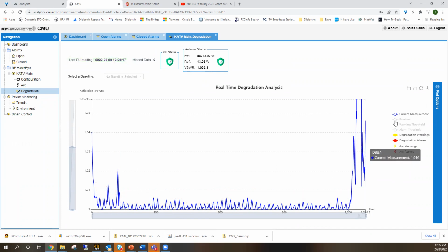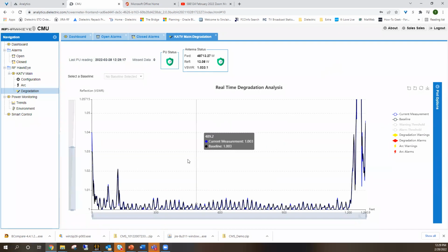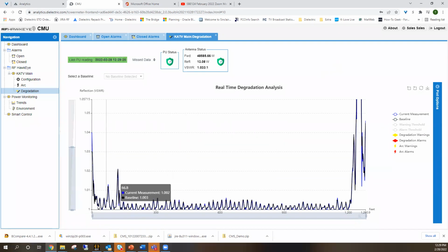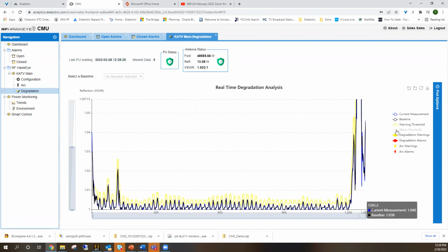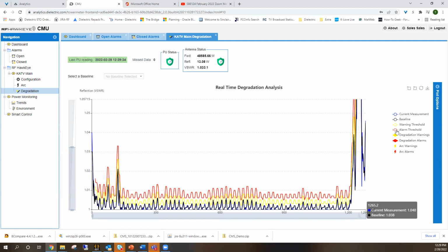So when you get your baseline when you first install and commission the system, that baseline is what is going to determine what your warning threshold and then your alarm threshold is going to be. Currently, we have an algorithm that determines what those thresholds are. They can be set to anything you'd like. So if you know the performance is going to get worse over the winter months, then you can go in and change that.